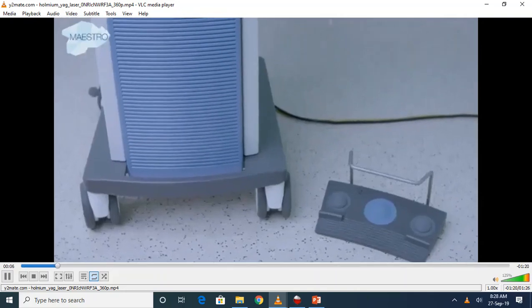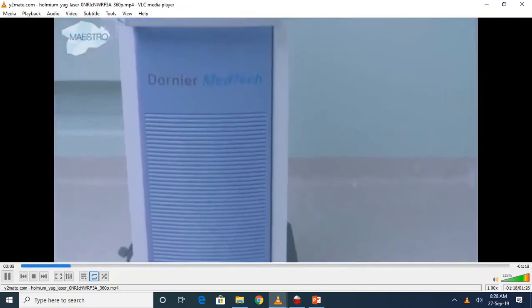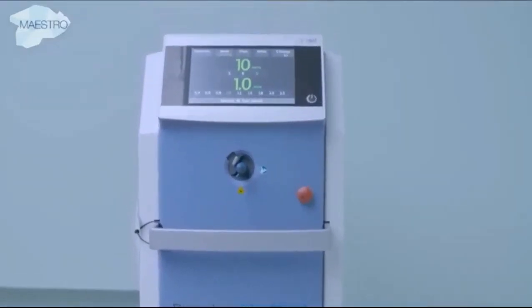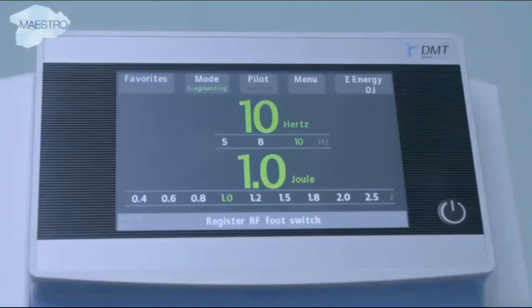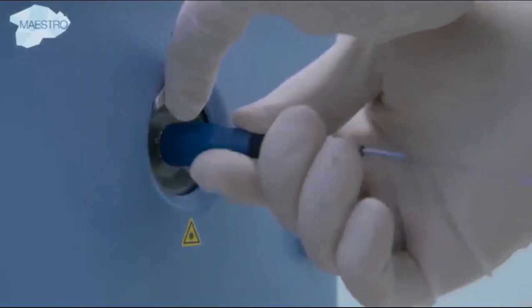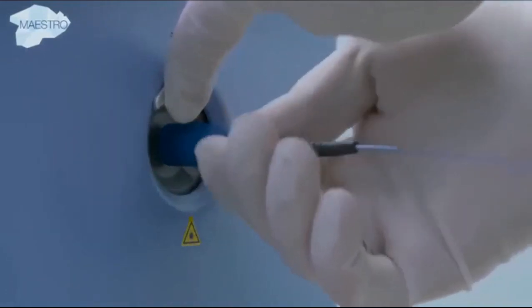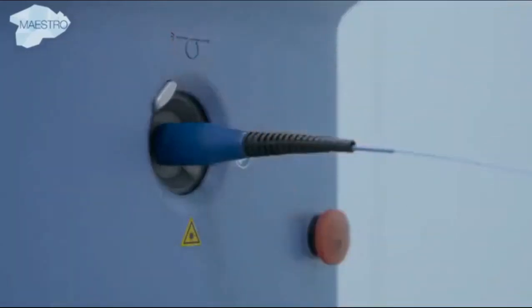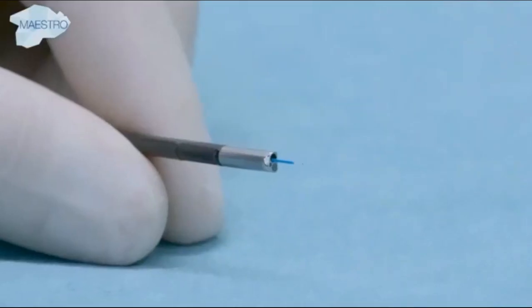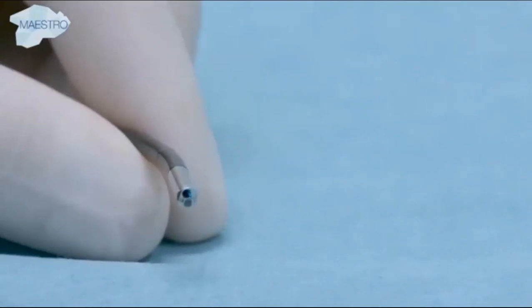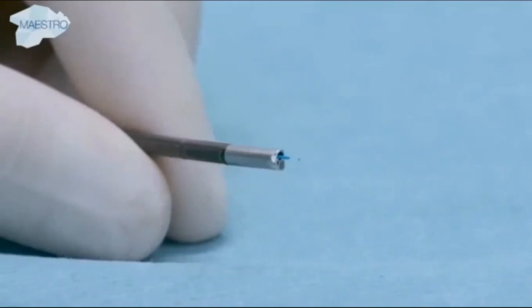The holmium YAG laser is a solid-state laser made with the rare earth element holmium in combination with a yttrium aluminum garnet crystal. It operates at a wavelength of 2100 nanometers, which falls in the infrared spectrum and is therefore invisible to the human eye. The laser energy is transmitted via a flexible silica fiber with a diameter ranging from 200 to 400 microns when used with a flexible ureterorenoscope. The fiber should always be visible for the user in order to protect the endoscope from damage.